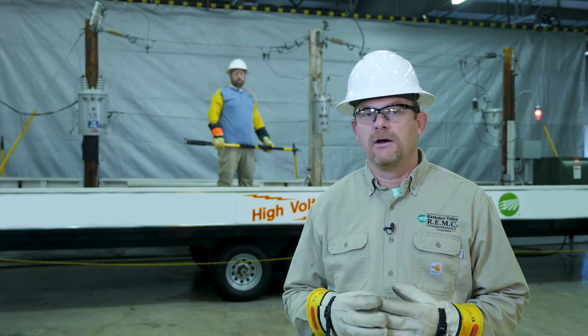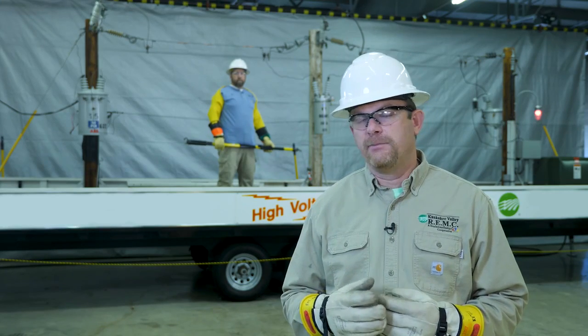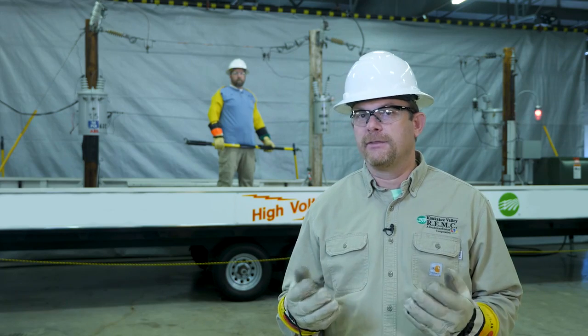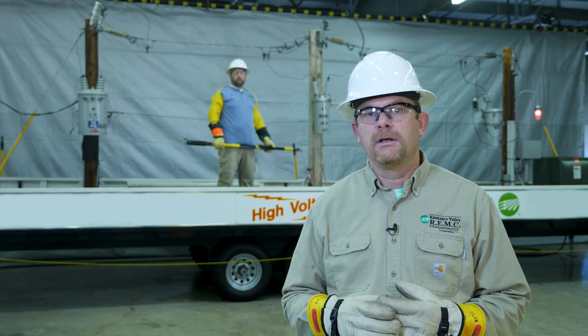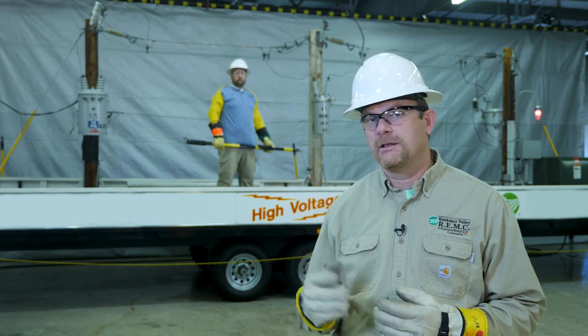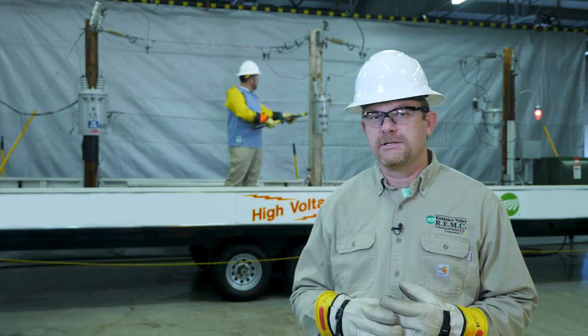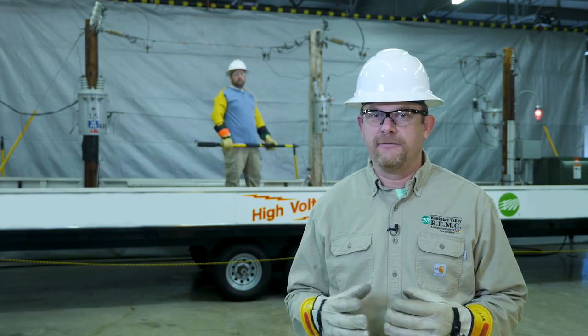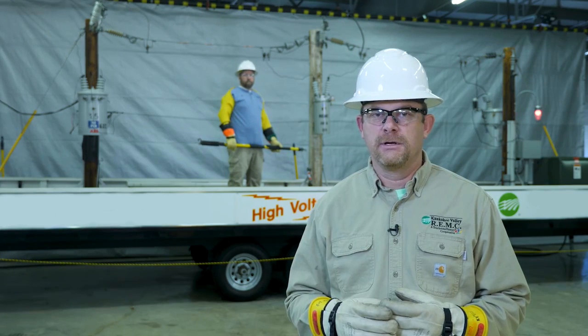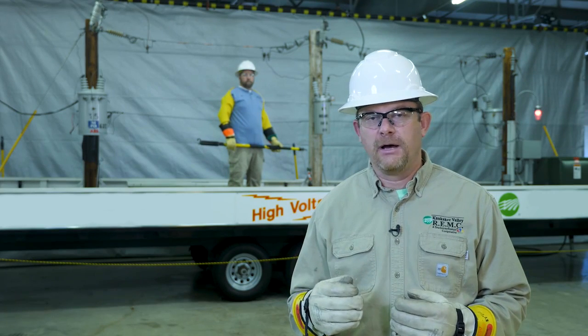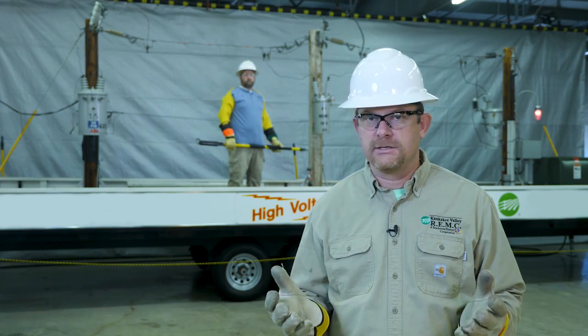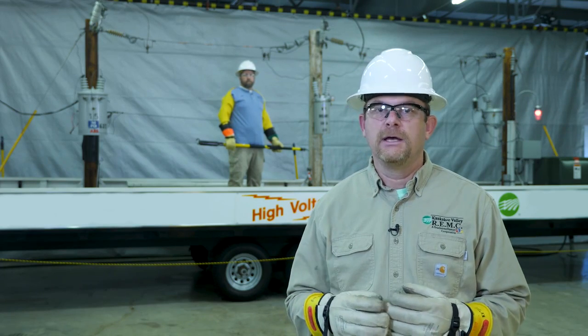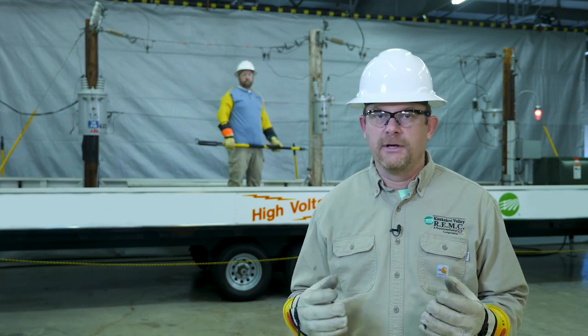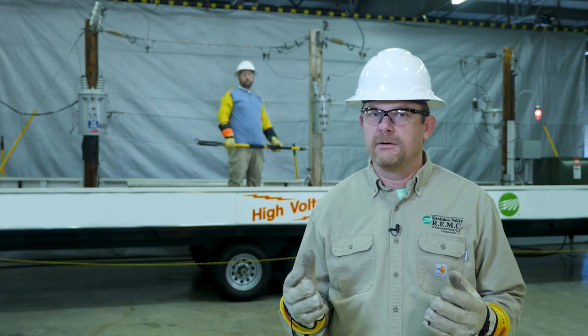Now imagine you're sitting at home on the same sunny day and your power blinks off 1, 2, and 3 times and then goes out. This blinking is due to a recloser like the one on the center pole working as it should, but acts a little differently than a fuse when a ground fault occurs. This momentary interruption in power is designed to allow whatever caused the ground fault to clear itself. If the cause were to clear itself, the power would not completely go out.